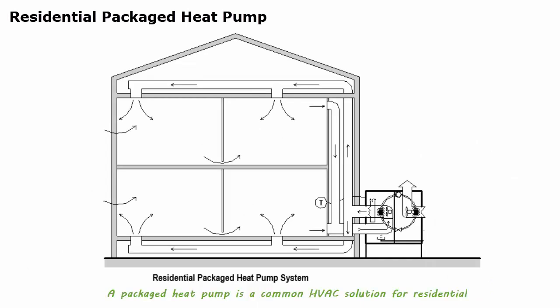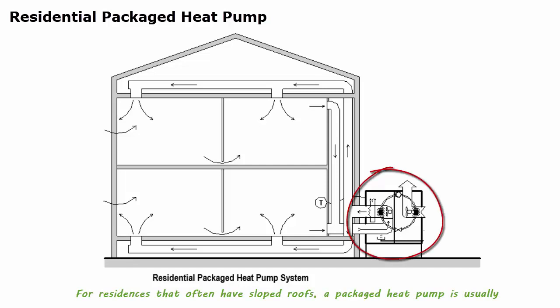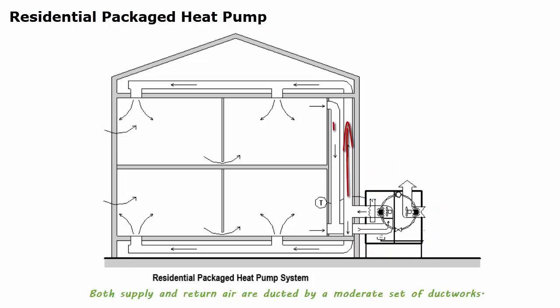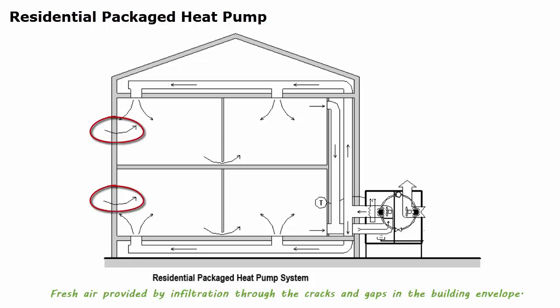A packaged heat pump is a common HVAC solution for residential or small commercial buildings. For residences that often have sloped roofs, a packaged heat pump is usually located to the side of the building. Both supply and return air are ducted by a moderate set of ductworks. Fresh air is provided by infiltration through the cracks and gaps in the building envelope.